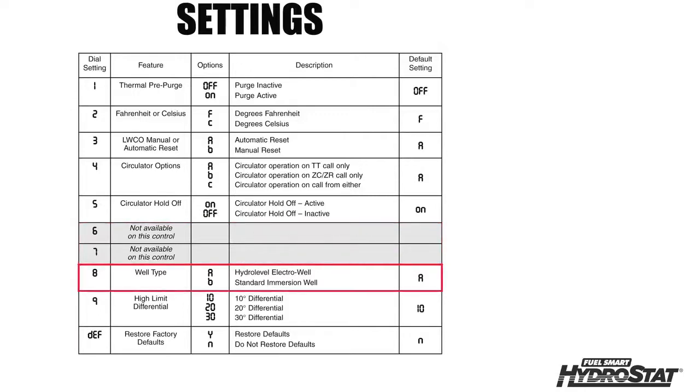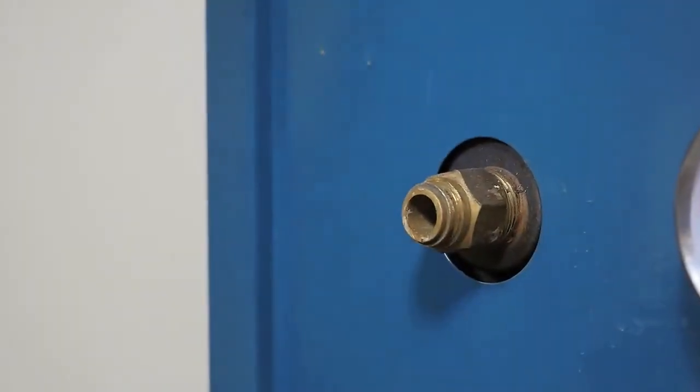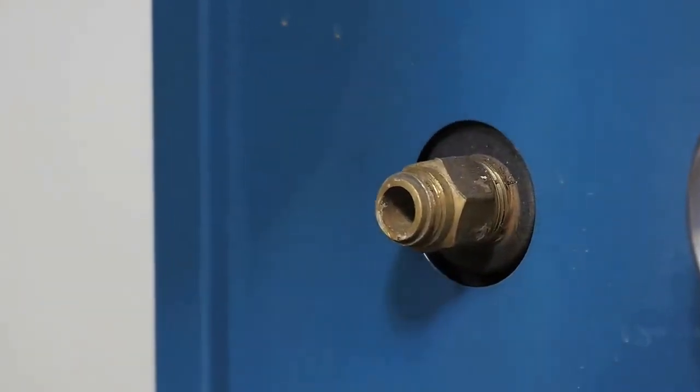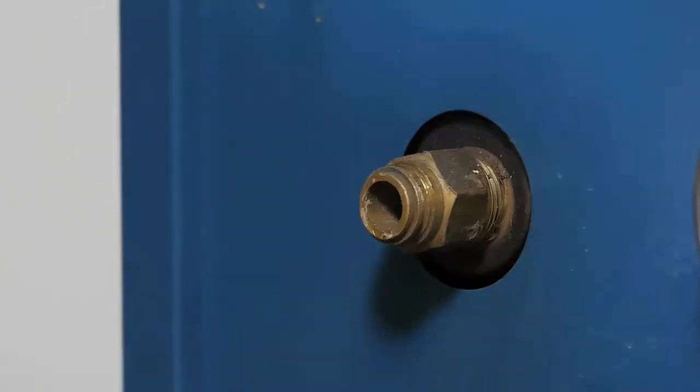Option eight is for setting the immersion well type. While the control is designed to automatically determine the well type, this optional feature can be useful when installing on a standard immersion well that contains hardened heat transfer grease or other contaminants.